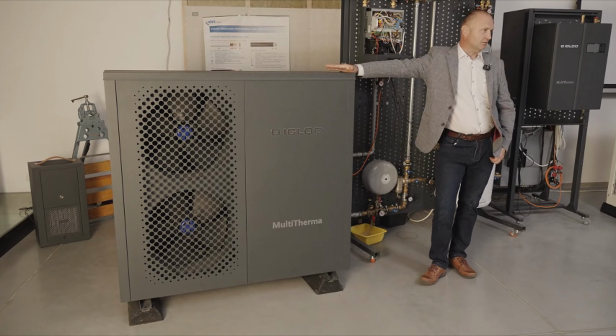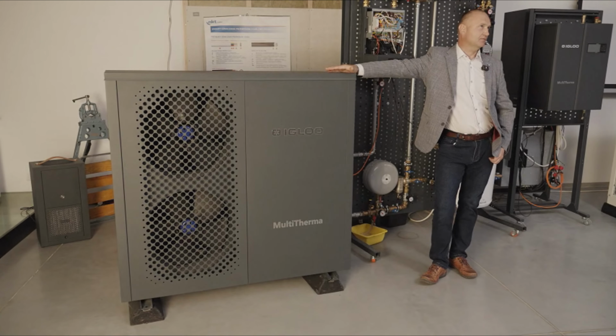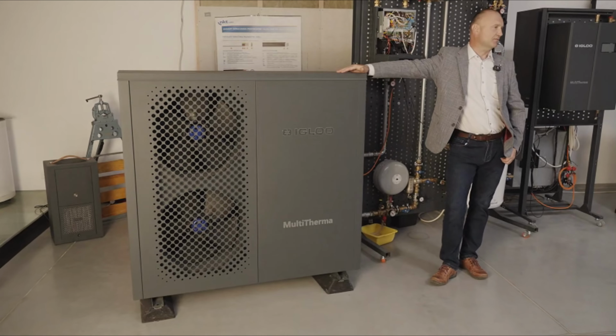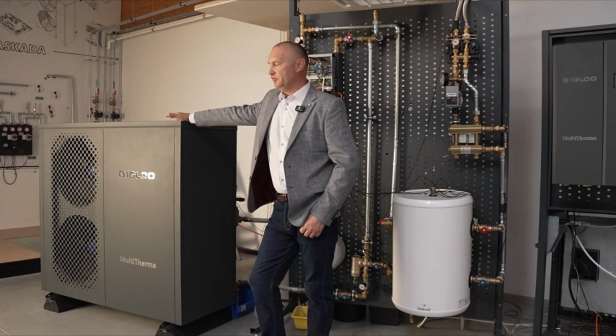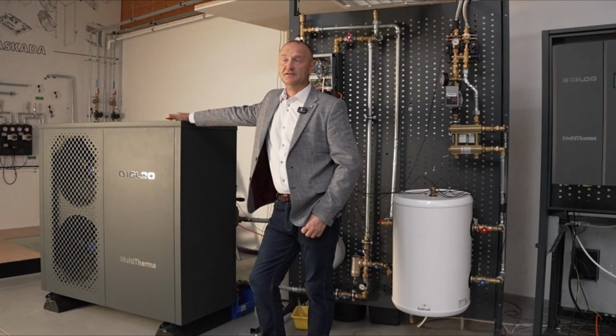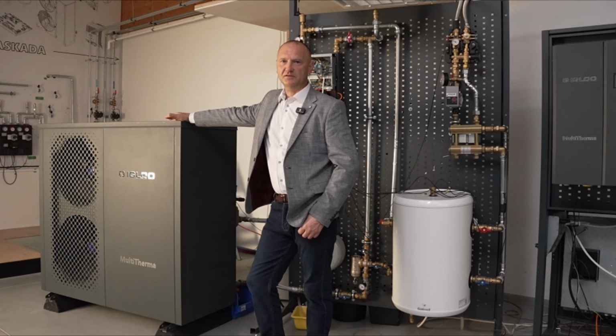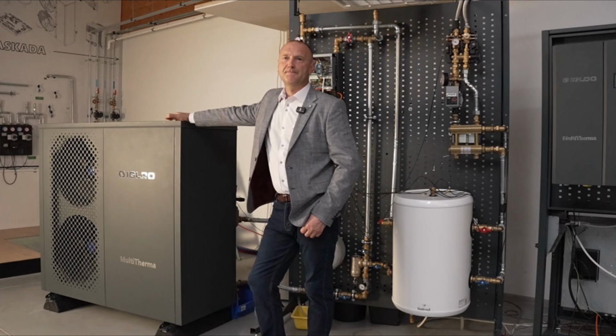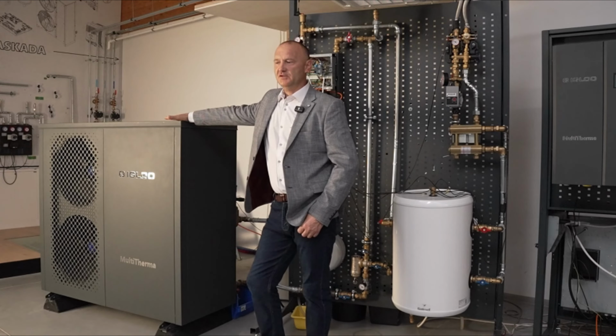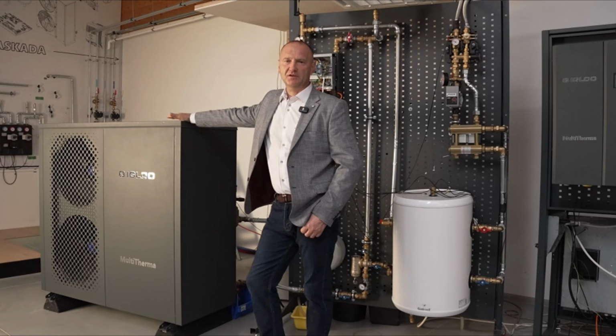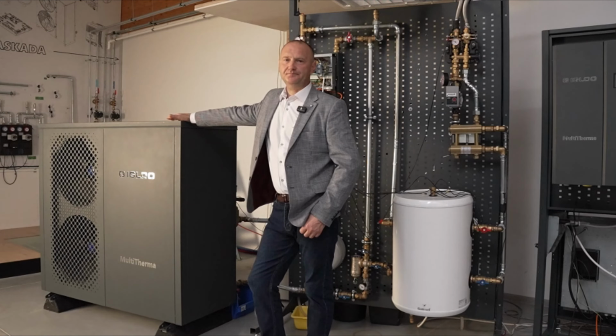Due to its inverter-based construction and the employment of a permanent magnet brushless 6-pole electronically commutated compressor, the load versus torque characteristic of such a compressor is such that the device operates more efficiently the lower the revolutions it runs at. So, consequently, this device, even when operating at high RPMs, has very high energy efficiencies. The COP of our heat pumps reaches even 5.5. However, the more modulated the pump, the higher the COP and the unit's energy efficiency.